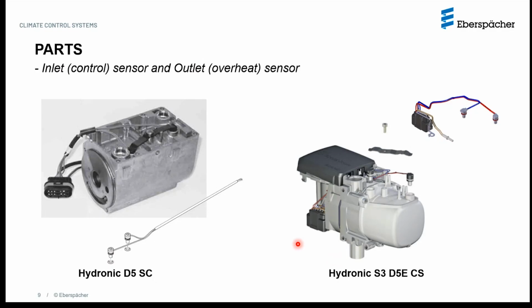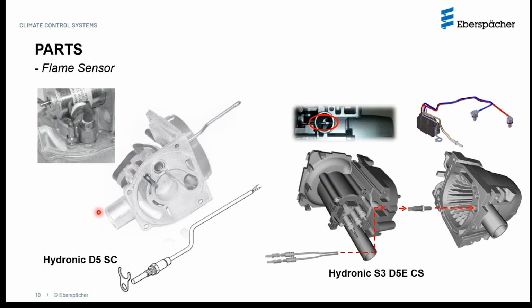All right, let's move on to the next slide. Here we can see the next sensor, which is again part of the whole lead harness assembly. It's called the flame sensor, and as you may have guessed, the flame sensor is what detects the flame. The flame is detected when the heater tries to successfully start. This detection is done by measuring the temperature of the hot exhaust gas when the fuel is ignited and begins to burn. The exhaust leaves from the exhaust port, which has an exhaust tube connected to it, and as you can see, the flame sensor is seated directly in its path. This applies to both.